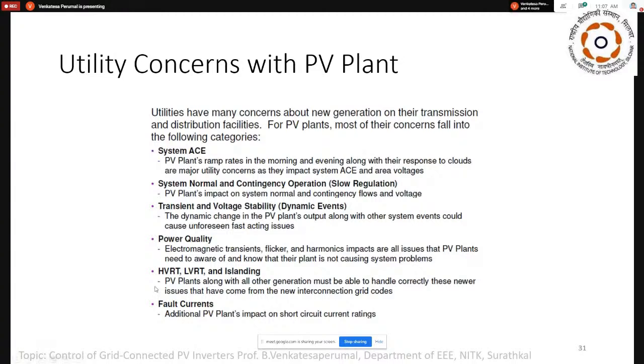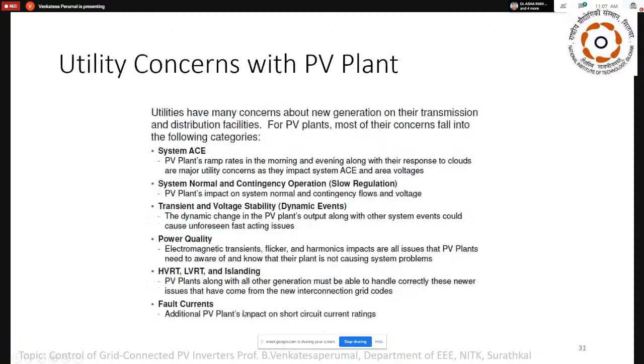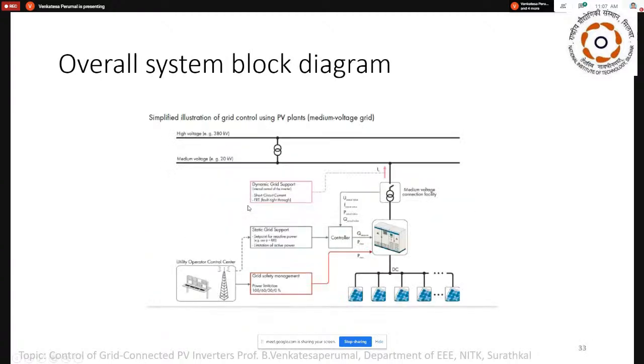Exactly, I was talking about power quality, high voltage ride-through, low voltage ride-through, and islanding. These aspects need to be covered: the system ACE and normal contingency, power quality, high voltage ride-through, low voltage ride-through, islanding, and fault currents. So these are all the concerns from the utility point of view before putting the PV plant into the system.